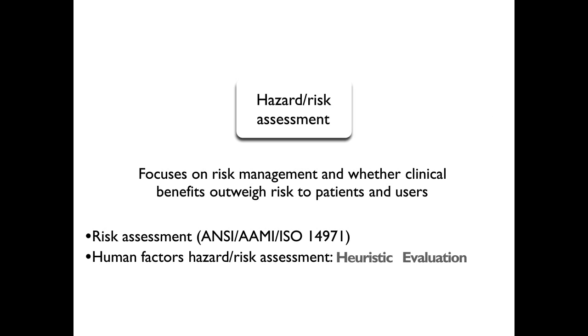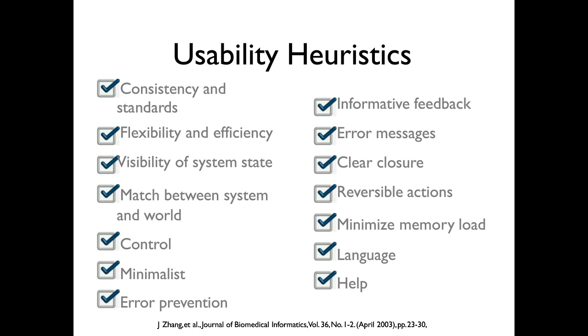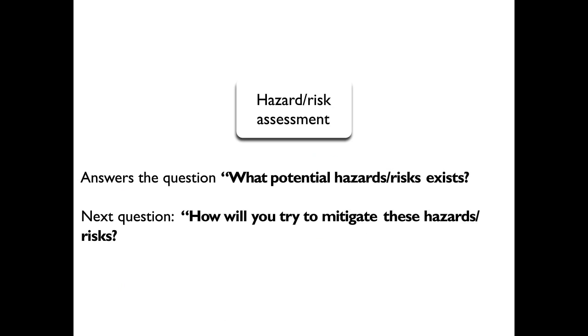And of course, manufacturers have a process that they go through. There are different regulations that they have to abide by. But as human factors specialists, we often help out with this through a technique called heuristic evaluation. Basically, we'll look through the different medical devices and ensure that they're not violating basic principles of good design. So the hazard risk assessment answers the question, what are the potential risks or hazards that exist with the medical device?